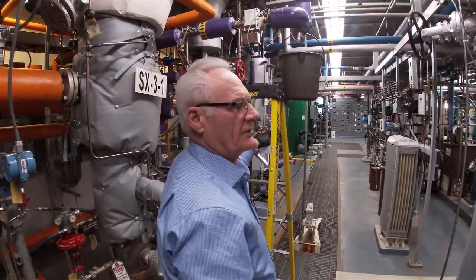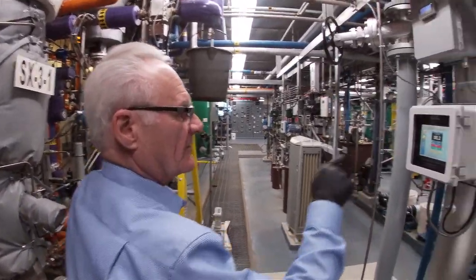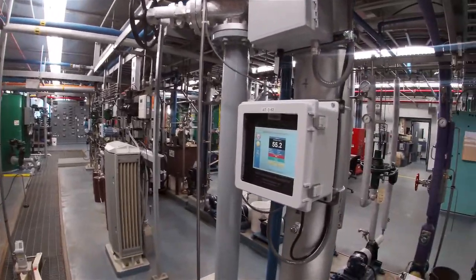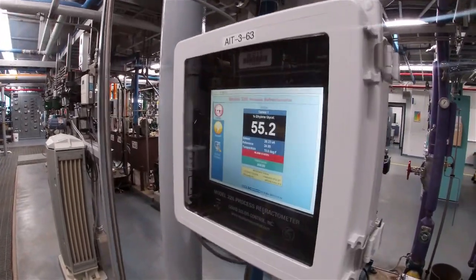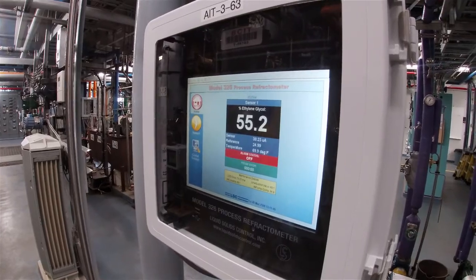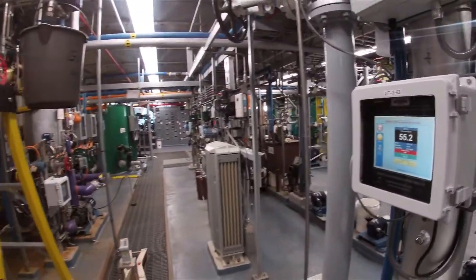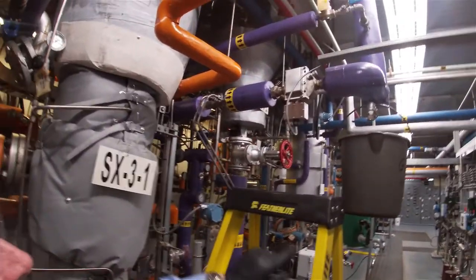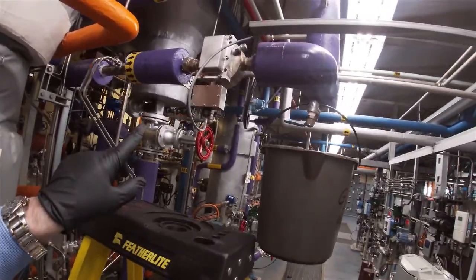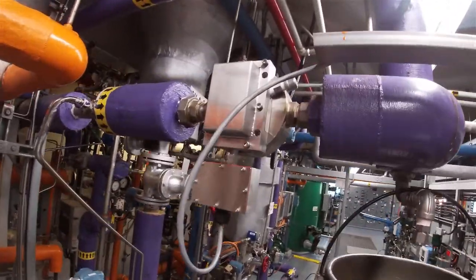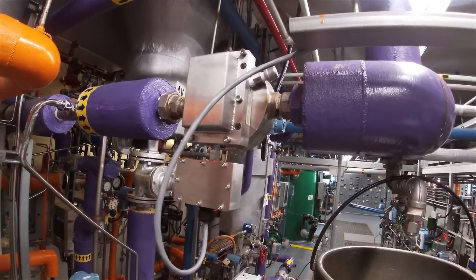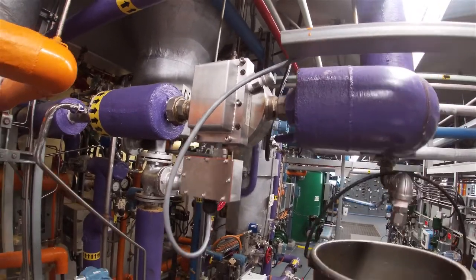Okay, what we're going to do today is calibrate a refractometer on the recirculating ethylene glycol for a second effect. The electronics are right here. It's showing right now 55.2% signal. The actual sensing element is sitting up here on a recirculation line. And what we've got to do with this line is drain it first.